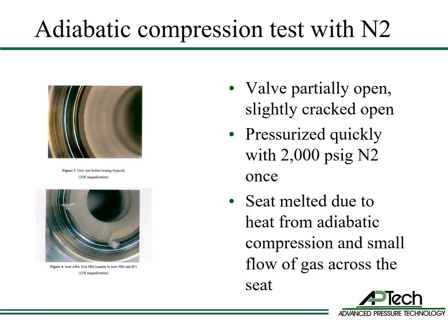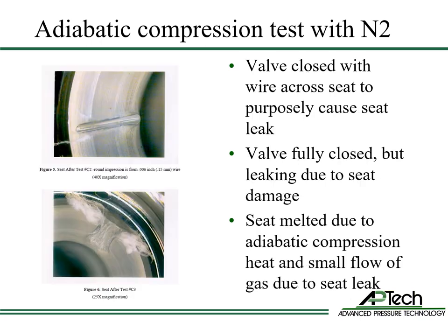While the classic adiabatic compression failure is oxygen and residual oils, even inert gases and polymers can experience adiabatic compression failures. In this test, a valve is partially opened and pressurized quickly one time with 2000 psi of nitrogen. The PCTFE valve seat melted due to the heat from compression and the small flow of gas across the seat. In another lab test, a valve is closed with a small wire across the seat to purposefully cause an across-the-seat leak. The seat melted due to adiabatic compression heat and the small flow of gas due to the seat leak.